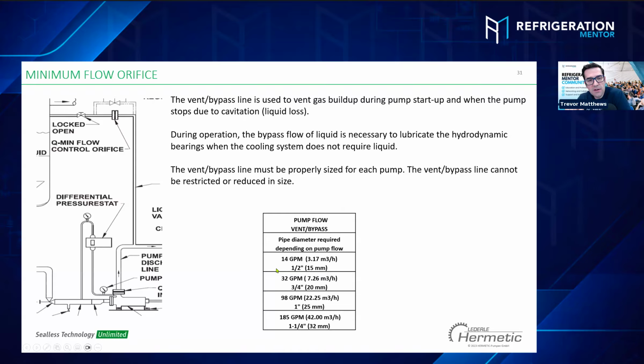If on the discharge, when it's coming out, you get any bubbles or any flash gas, that line is going to vent it off. So that ball valve that I see up there should never be closed, is that correct? Yes, it should be locked open, never closed. Because if that's left closed by someone, what would happen? In some point, the pump is going to stop on high differential pressure.